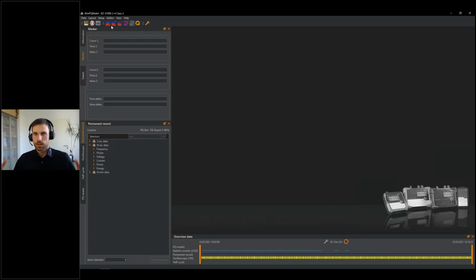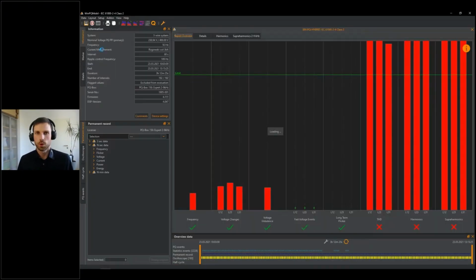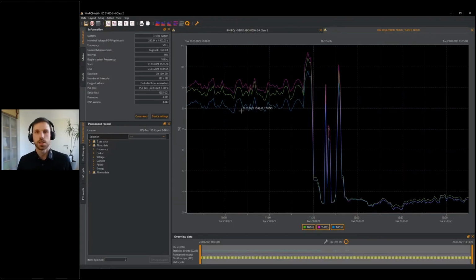So I can see the whole measurement file, 3 hours long. I go to norm evaluation and check the values. So I, for example, want to check, oh, superharmonics, harmonics, and THD is bad. Well, I click on the THD and see the timing diagram. Well, it was bad at the beginning of the measurement of the recording, and then it dropped. And at the end, it was good.